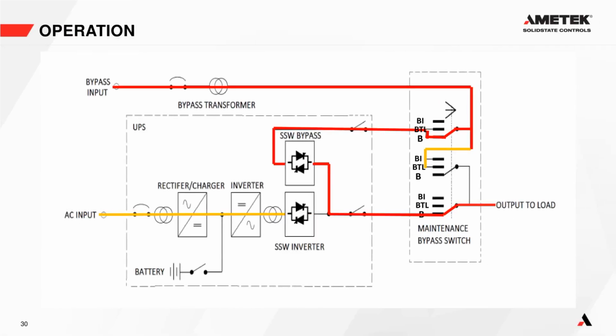Now the next position is bypass to load. Okay, now before we go to bypass to load, and I'm always going to have this normal here, before we ever move the switch from normal to bypass to load, we always have to make sure we press the bypass to load static switch push button. It's very, very important, because that way we are always paralleling when we move this switch between normal and bypass to load. It's a make before break switch.